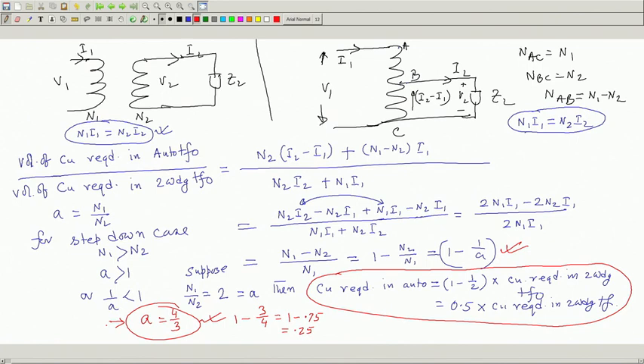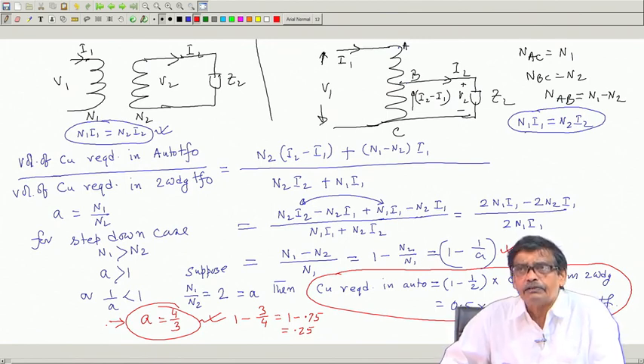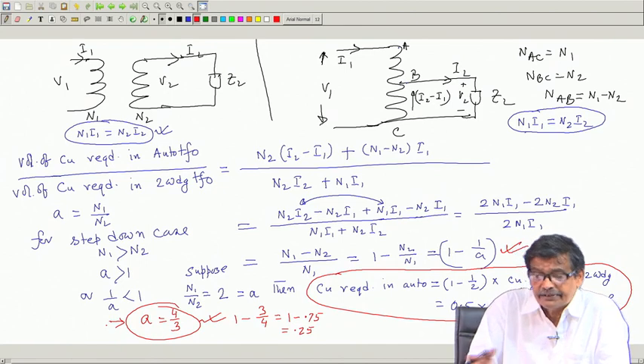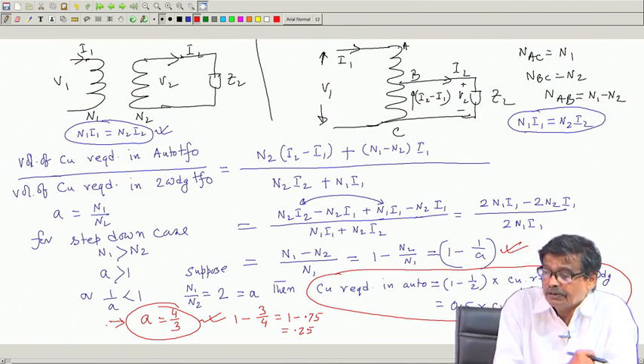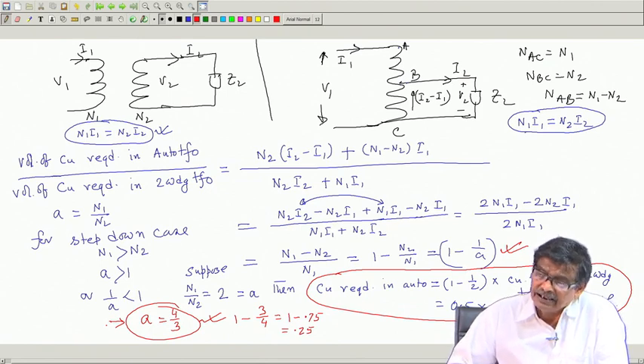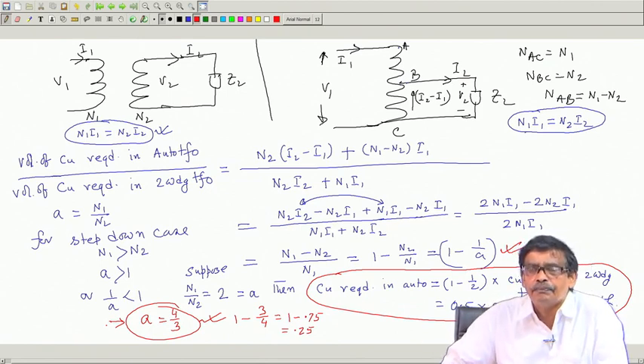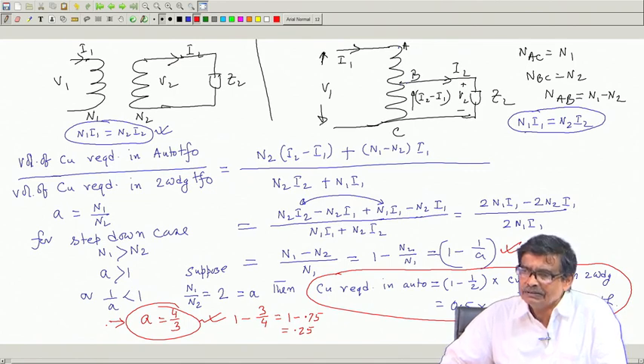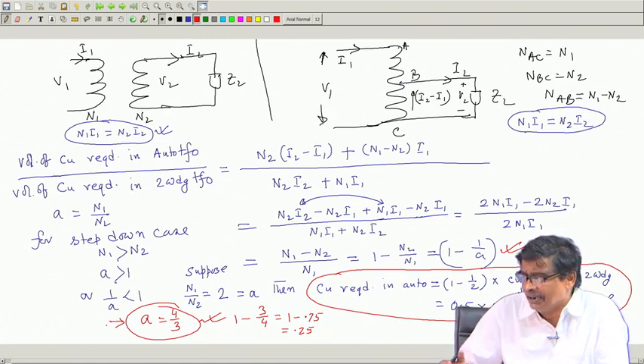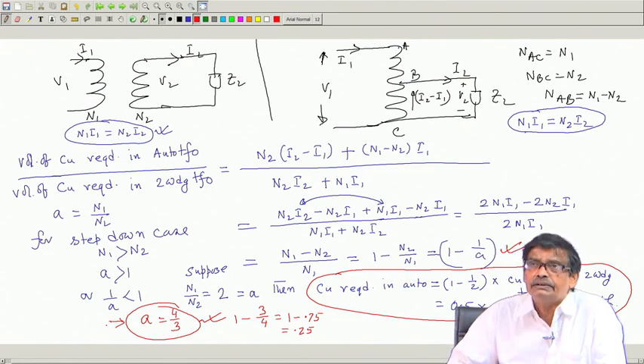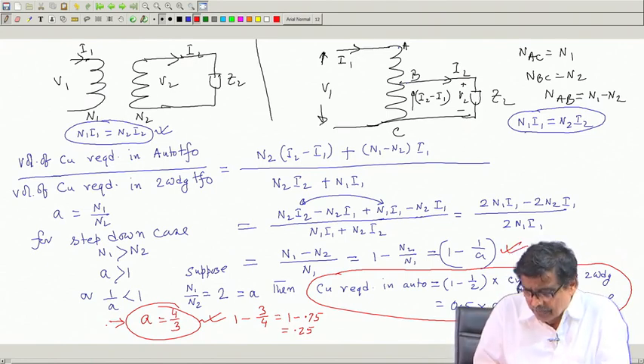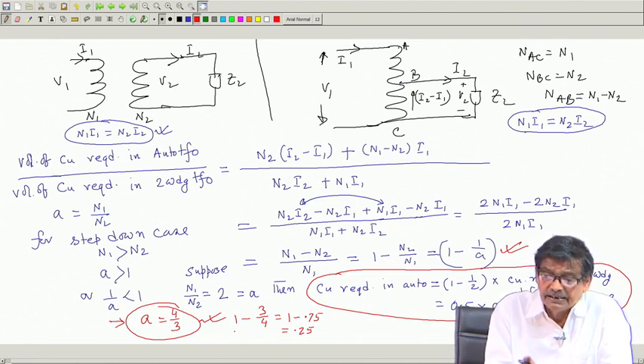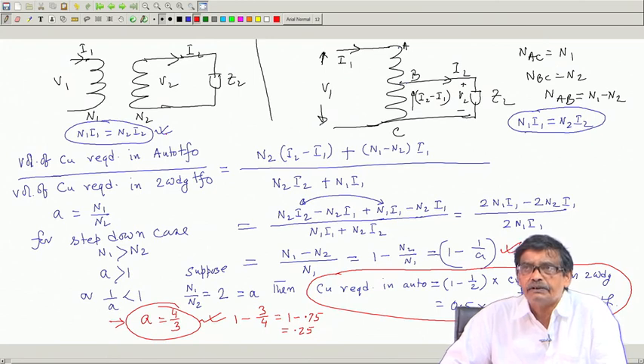So wherever you require a voltage transformation, two candidates are there: a two winding transformer or an auto transformer. It looks like you should always go for the auto transformer, since less copper will be required. Whether that savings is really significant is a secondary issue, but mathematically we note that savings will always take place no matter the value of A, as long as A is greater than 1 here.